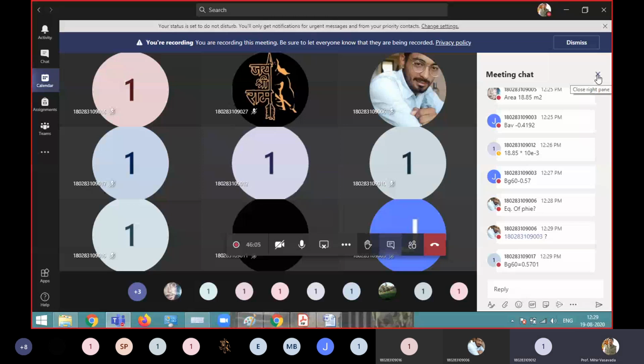नहीं सर एक्चुअली मेरा क्वेश्चन ऐसा है कि सपोज ट्रांसफॉर्मर आपने पढ़ाया था ना कि जो योक और लेग को जब ज्वाइन करते हैं ना तो वहां से जैसे टर्न होता है तो डेंसिटी में डिफरेंस आता है तो उसकी वजह से टर्बुलेंस क्रिएट होता है, मैग्नेटिक टर्बुलेंस. राइट. तो उसमें द फ्लक्स पाथ इज अलोंग द स्ट्रेट लाइंस अलोंग द ग्रेन ओरिएंटेशन, राइट? और व्हेन यू आर जॉइनिंग देम एट 90 डिग्री the grain orientation will change at perpendicular directly. So उसके लिए you have the turbulence over there and that's why we are using mitre joints so that this grain will cross each other at 45 degree.